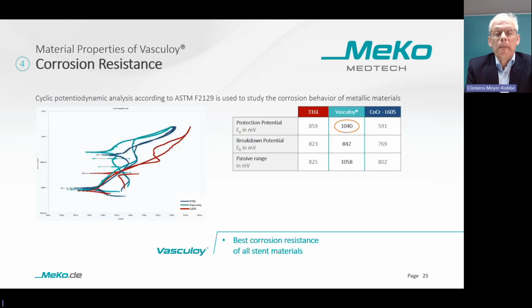Corrosion resistance is important to avoid any release of heavy metal ions. The corrosion resistance is measured by a cyclic potentiodynamic analysis according to the ASTM standard F2129. The graph on the left side of the slide is difficult to explain in a few words. To say it easily, the green-blue curve shows Vasculoy, and this curve is highest, which is good. That means it gives the best corrosion resistance. The interesting characteristic values for the corrosion are protection potential, breakdown potential, and passive range, with the protection potential as most important.